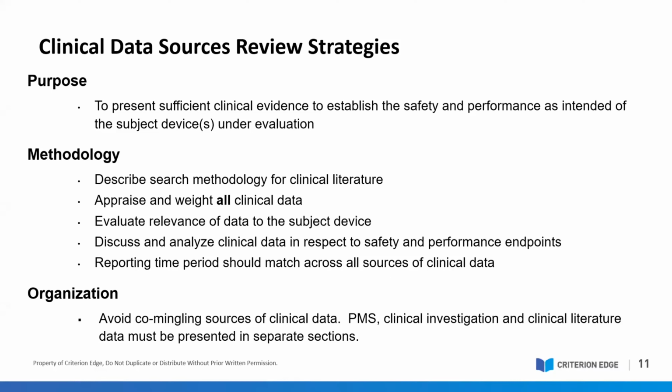This can include those data that have been identified through published literature or other publicly available sources, including registries. It could include PMS data that's been passively collected through your post-market surveillance processes. It could also include PMPF data that's derived from proactive post-market data collection activities that are conducted by the manufacturer. And it also could include some manufacturer-held clinical investigation data, although some companies say they don't have that type of clinical investigation data. The purpose, though, of the clinical data that you're including in your PER, that's clear.